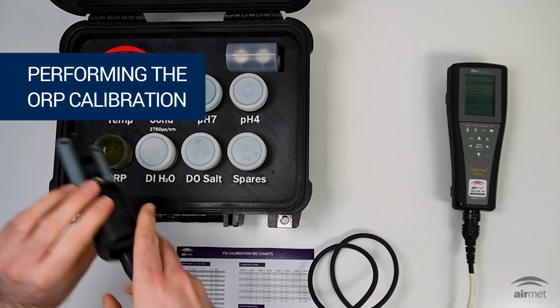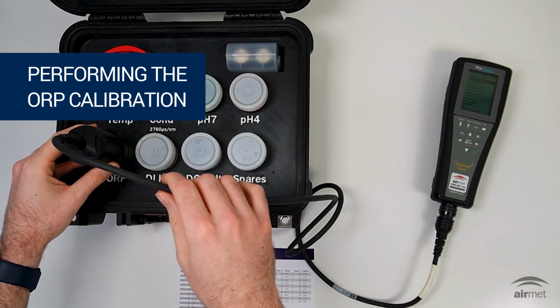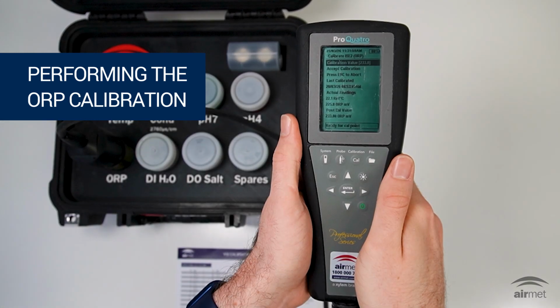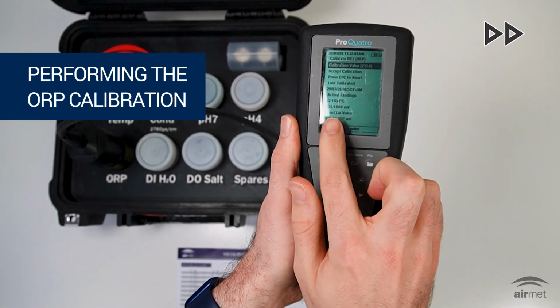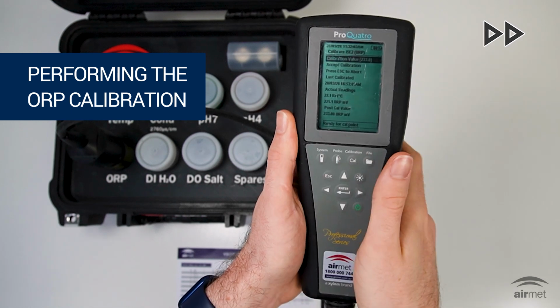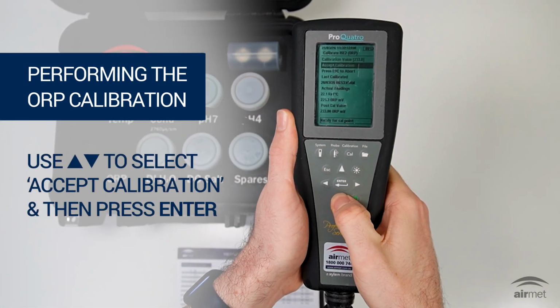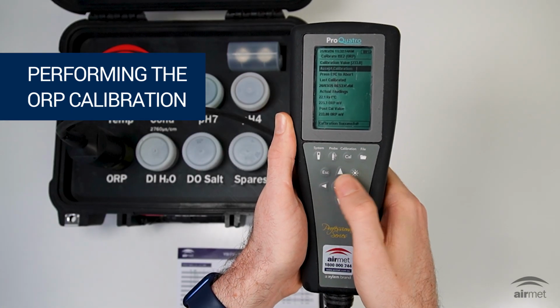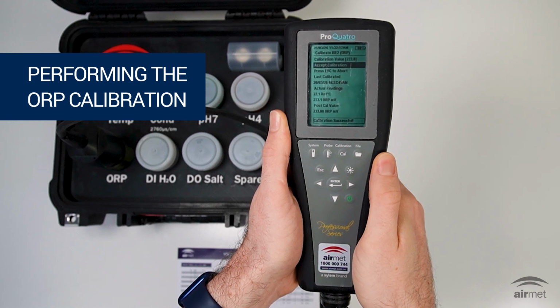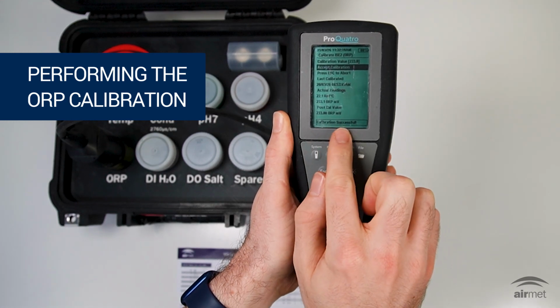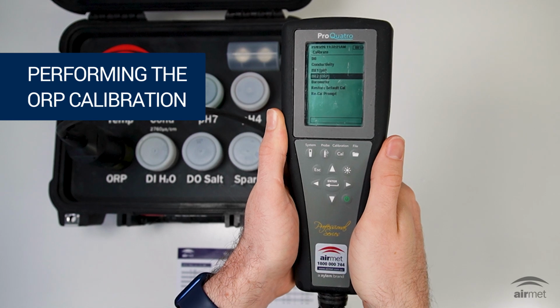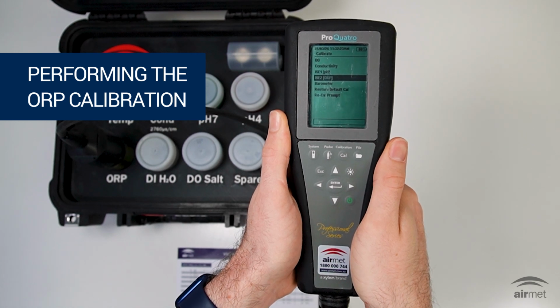Insert the probe into the ORP standard. Allow the readings to stabilize for roughly 1 to 2 minutes. Highlight Accept Calibration and press Enter. Once stable, the instrument automatically adjusts the offset to match the standard's millivolt value. A calibration successful message appears and the device returns to the calibration menu.